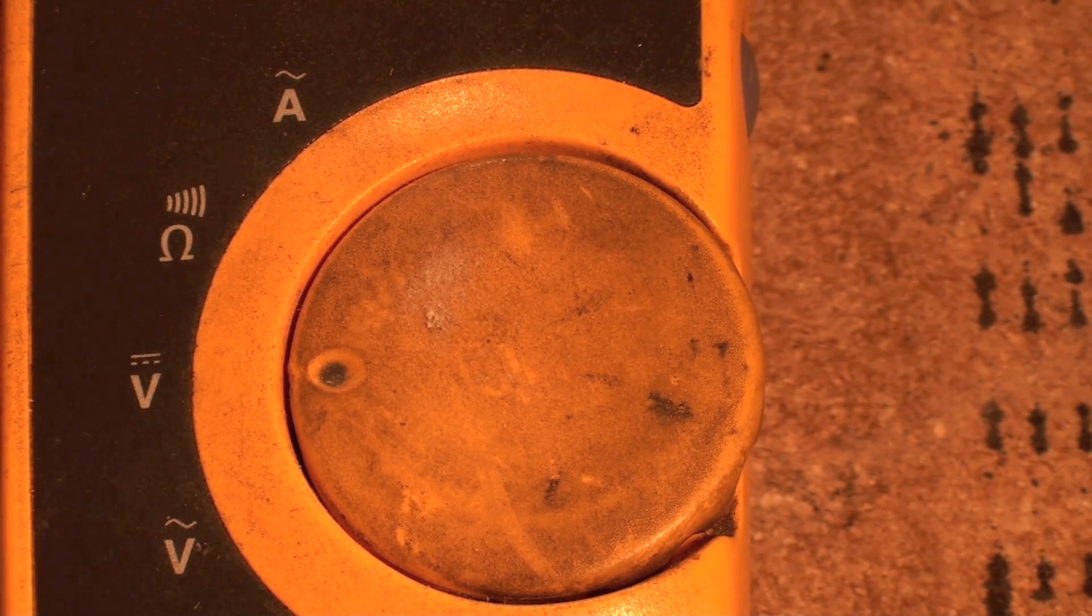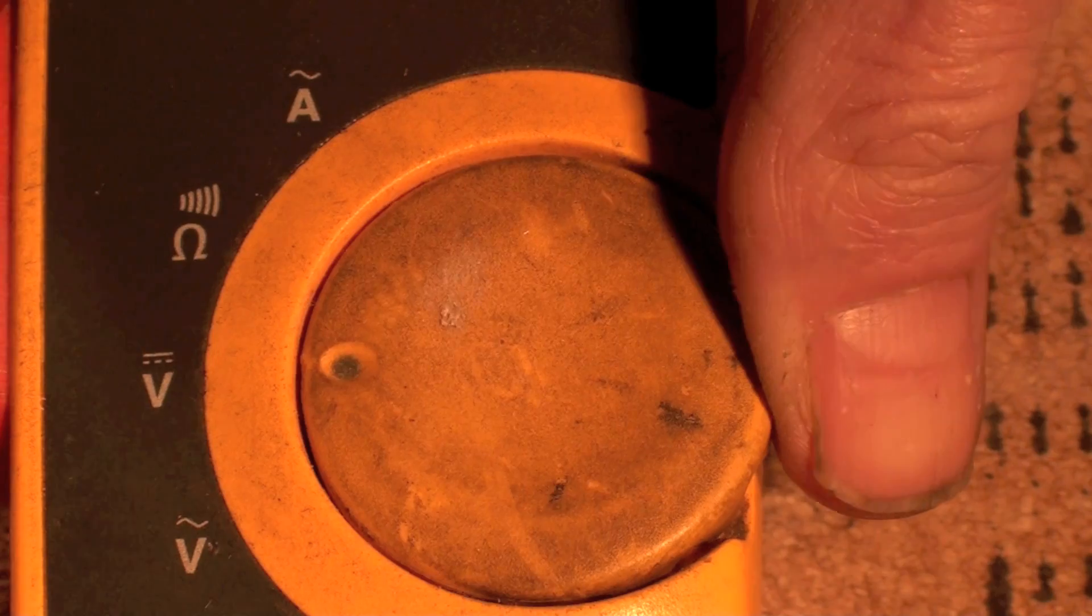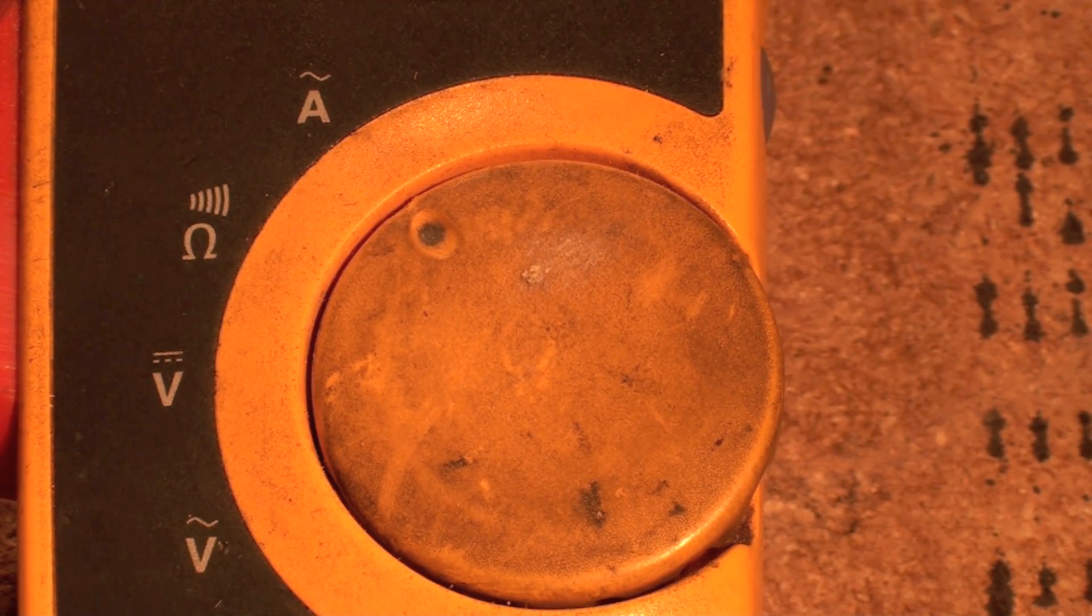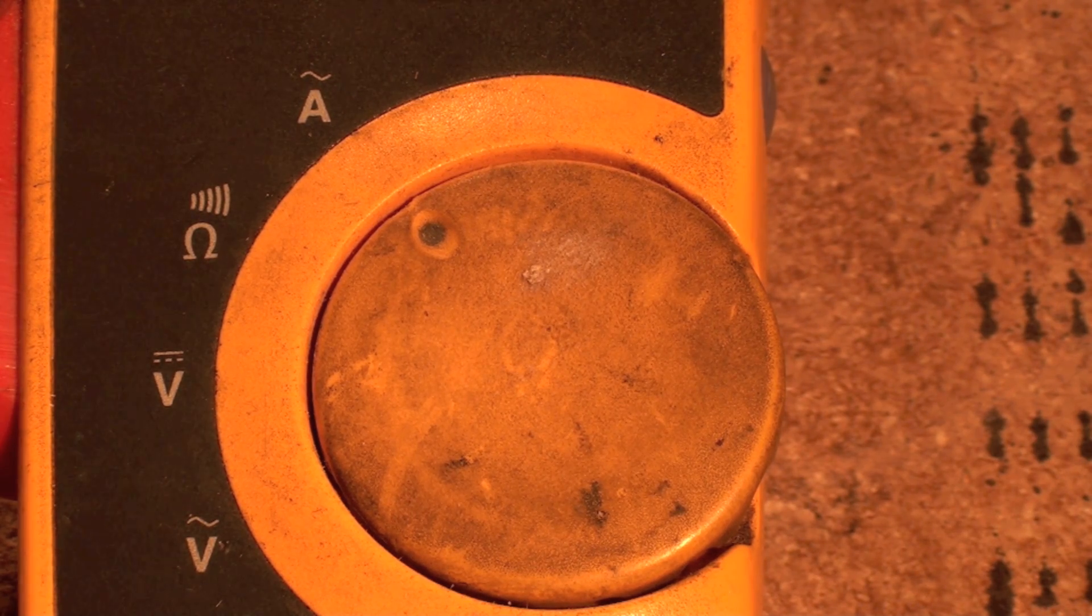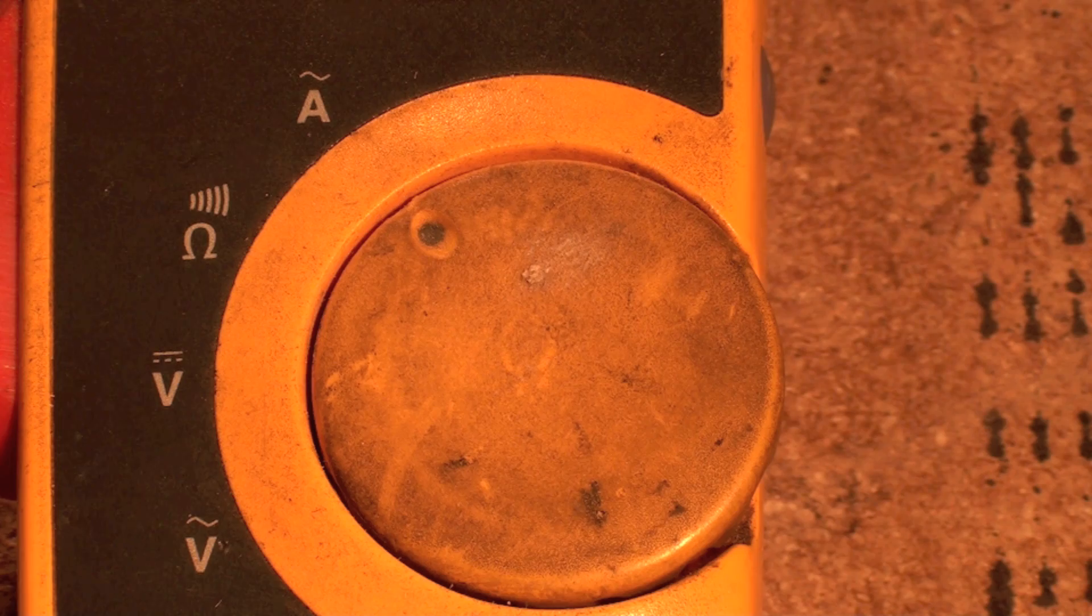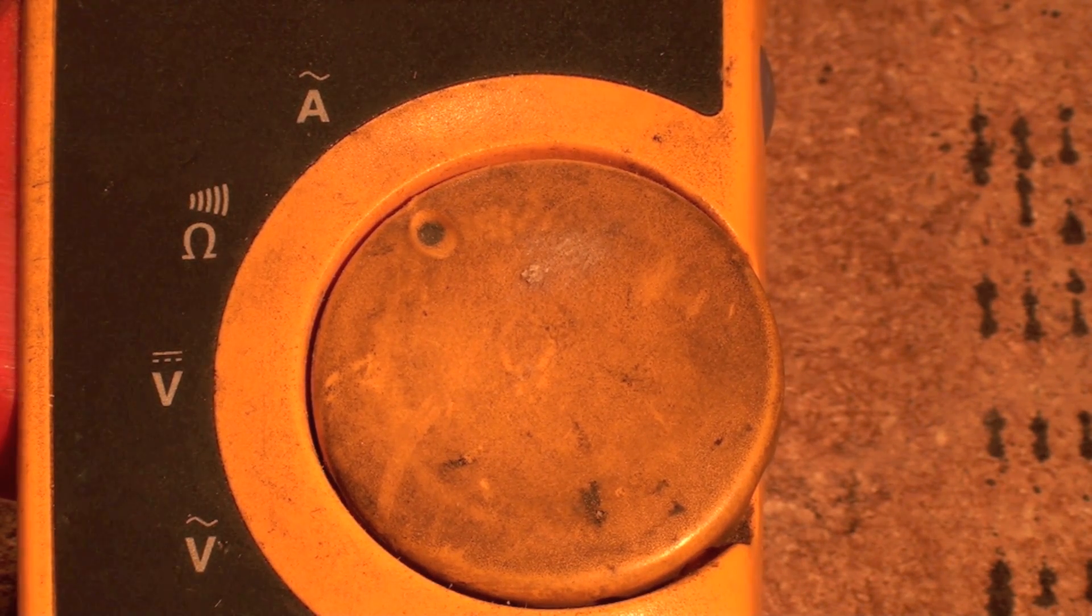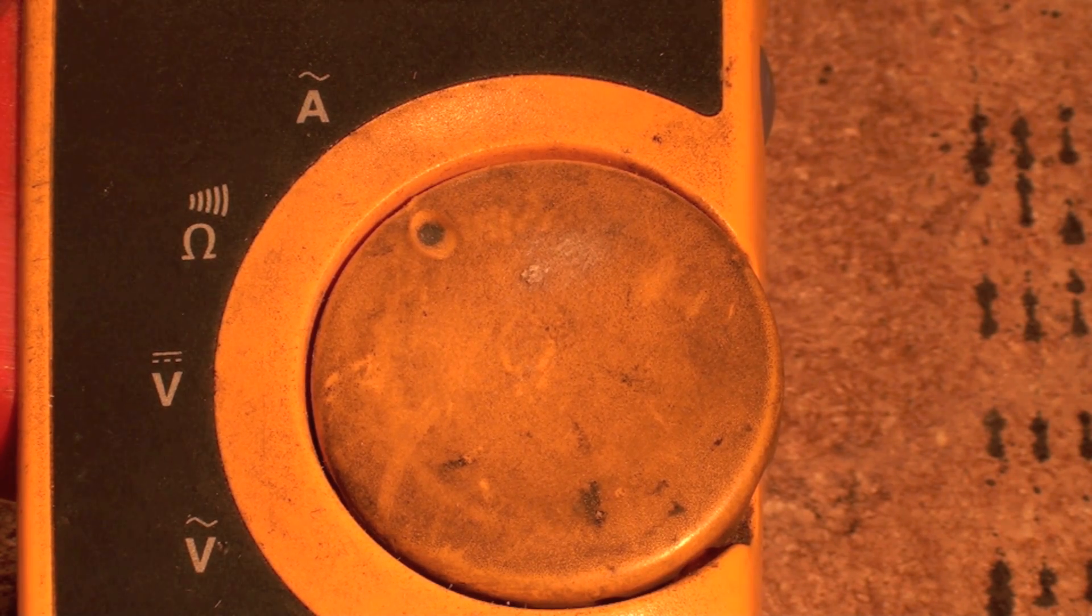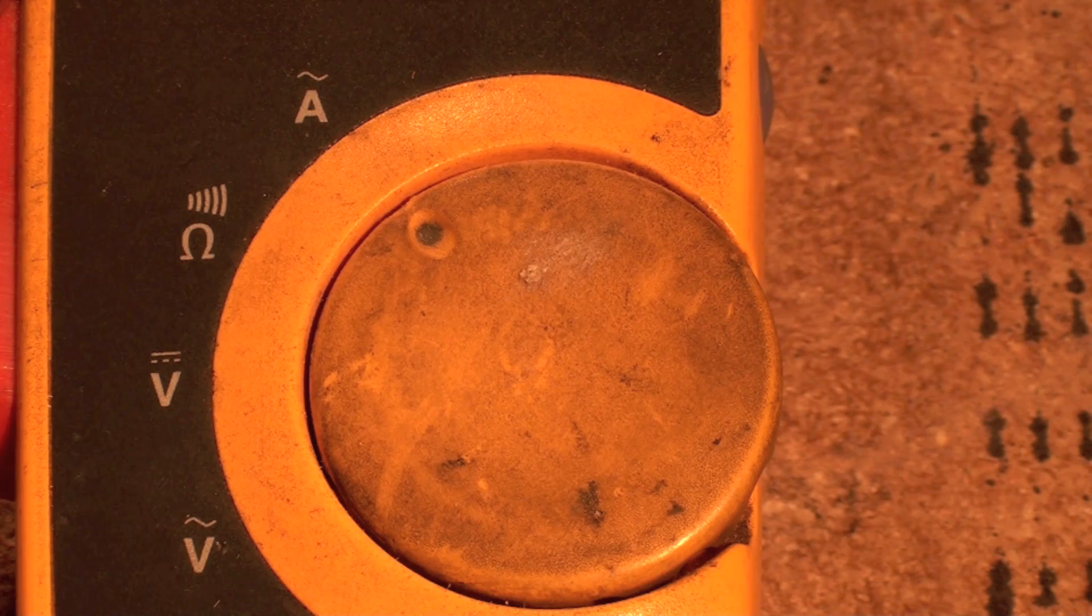The last position up here is AC amps. That's read by the clamp. When I close the clamp around one wire - you can't close around two, you've got to close around one wire - then I will read the amperage going through the wire. Very useful tool.